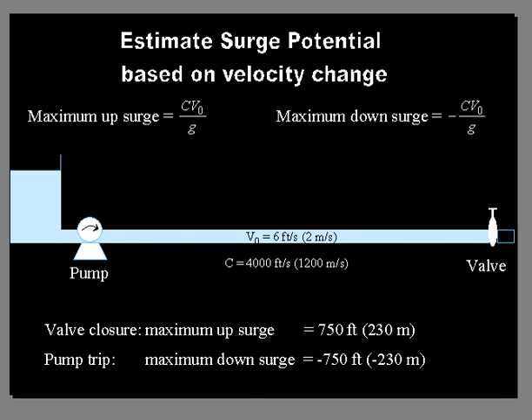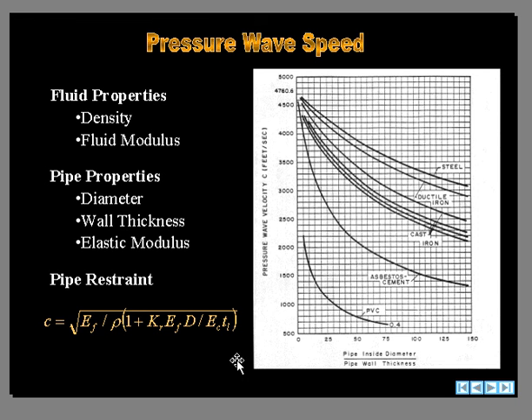The wave speed is given by this equation. As the thickness of the pipe decreases, the pipe is more flexible. We get a reduction in wave speed. So, there is some help in your surge 2000 that will help you calculate the wave speeds.